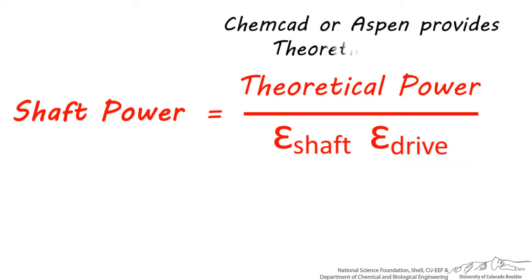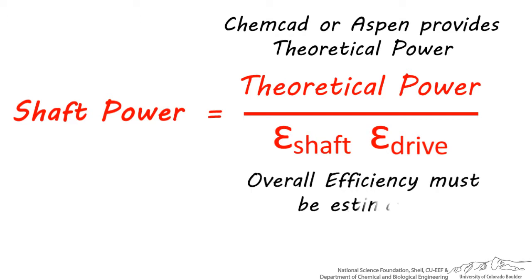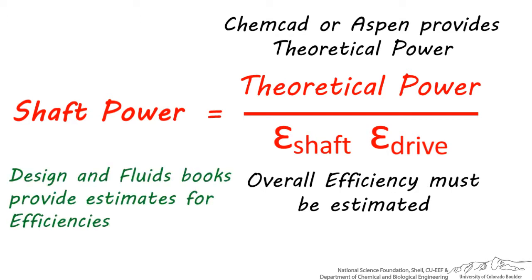While ChemCAD and Aspen do provide you with the theoretical power number, they will not calculate the shaft power for you. The reasoning behind this is that you must estimate the efficiency of the compressor or pump and the drive, because it can vary widely based on design specifications. You can estimate these efficiencies by looking at pump, turbine, and compressor efficiency tables in a fluids book, or you can use an estimate provided in a design book.